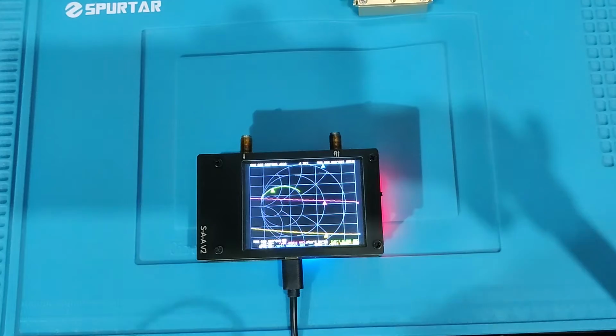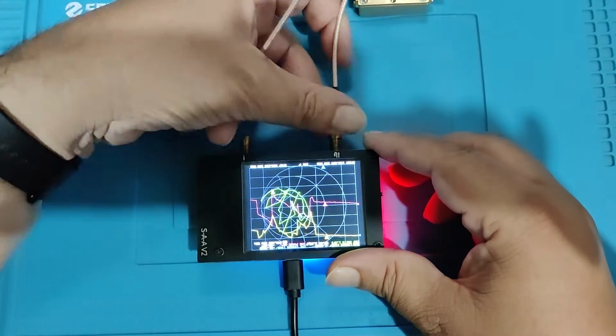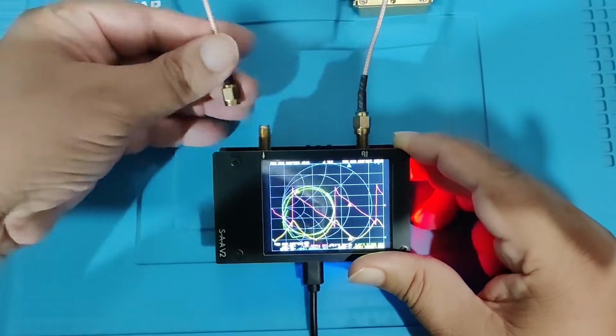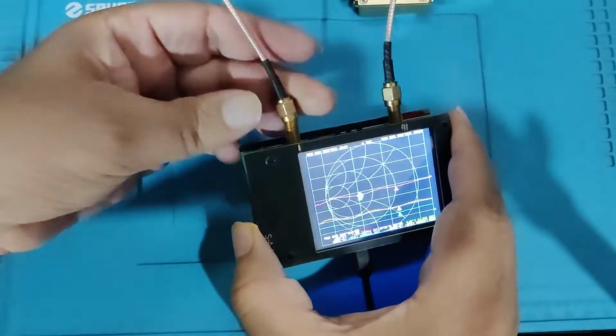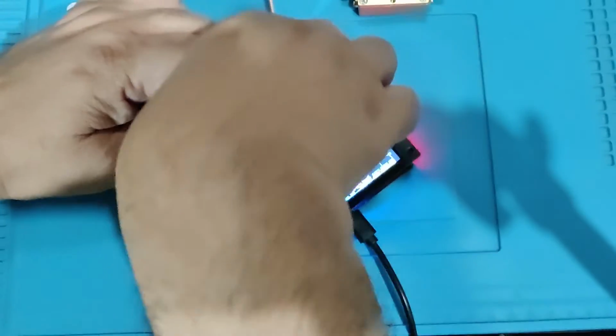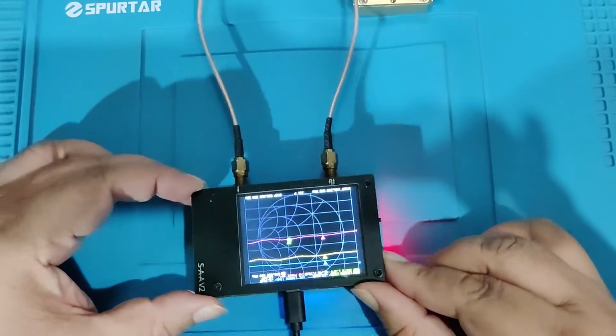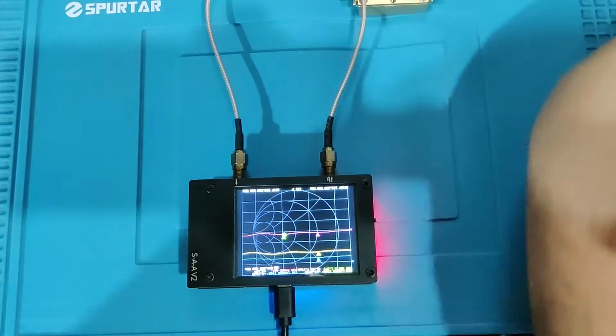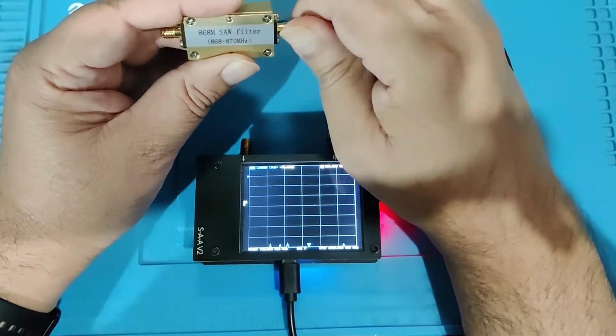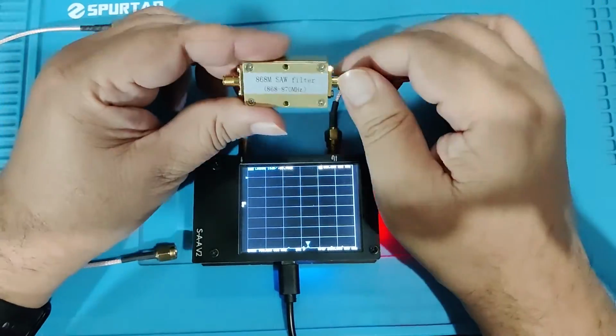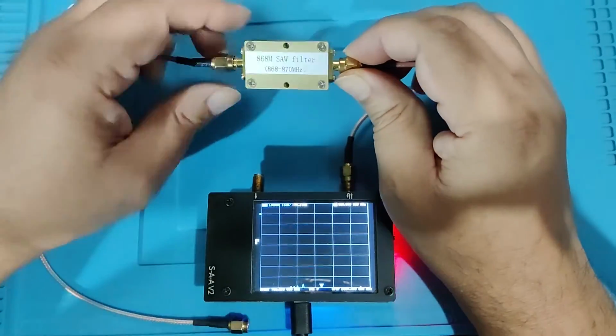After calibration, we will test both patch cables by attaching one end to the S11 port and the other end of the cable to the S21 port. We are looking for 0 dB loss or as close to 0 dB as possible. Once our cables are tested okay and the VNA is calibrated, we will go ahead and attach the filter with the help of these cables. These cables are 50 ohm cables.